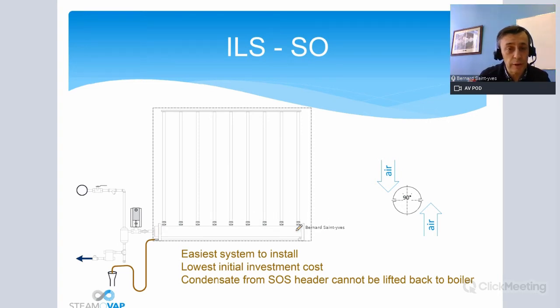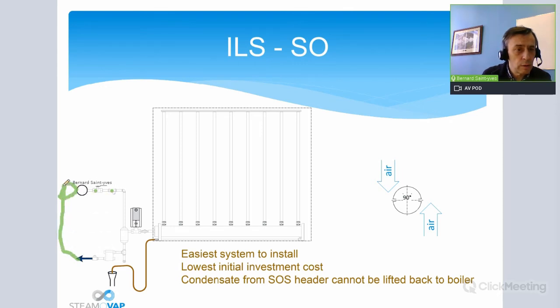So there is a header and vertical steam ramps. The header for us is always at the bottom part of the ramp, not like some others. Why? Because then if condensate accumulates here, you are safe. It has a very low chance of going inside the vertical ramp. The same way, you have the steam source here, a shutoff valve, a strainer, the filter, and then you go directly to the steam separator, where of course we remove the moisture or any condensate from the steam. You can bring this condensate to the boiler or the unfired steam generator, and then to the control valve, and you go directly here into the duct.